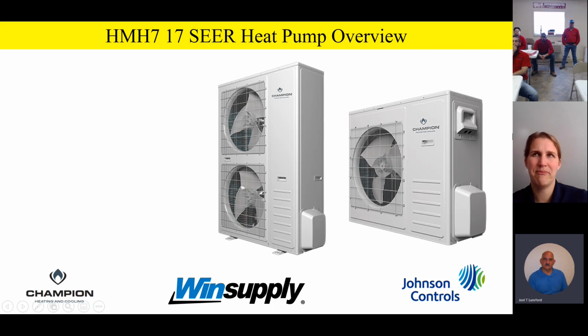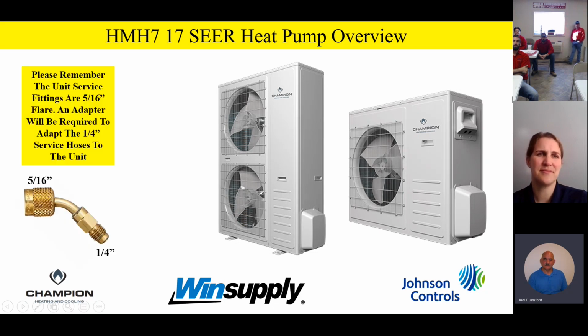So this morning we're going to start out with the HMH7, which is a 17 SEER heat pump. It's nominal 17 SEER. And by the way, it'll actually hold that SEER rating all the way up to the largest model. So that's pretty cool. And a couple things I'd like everybody to remember real quick too is that the service fittings on these things are actually 5/16 fittings. So you're going to want to make sure and have those adapters that go from 5/16 flare to 1/4-inch flare for your service hoses.